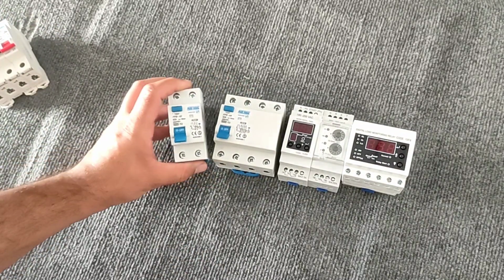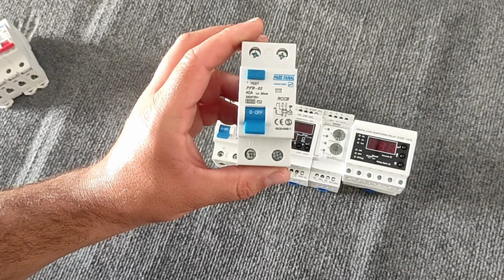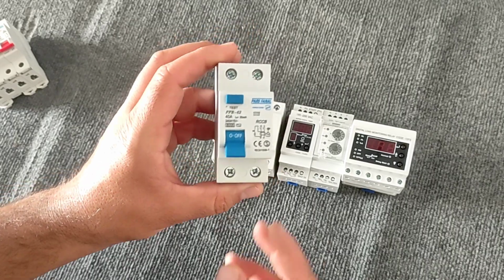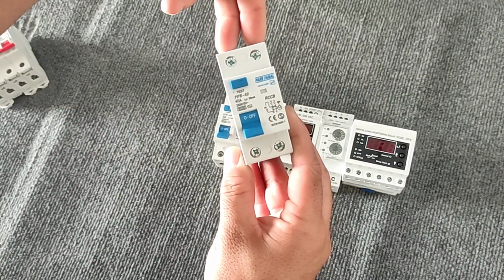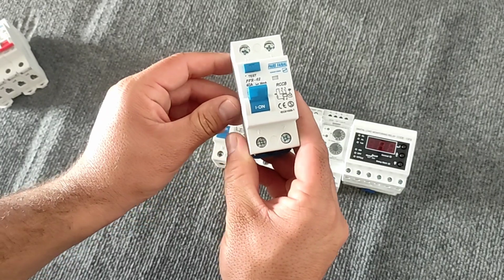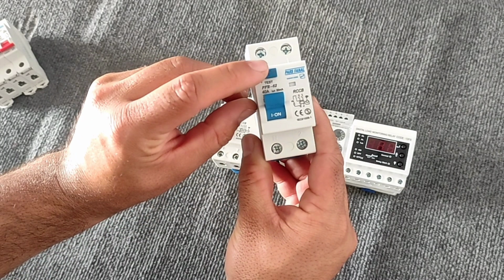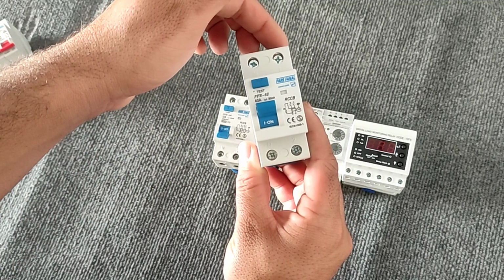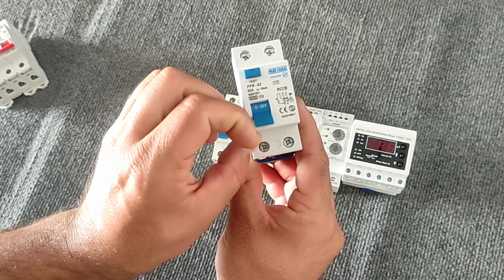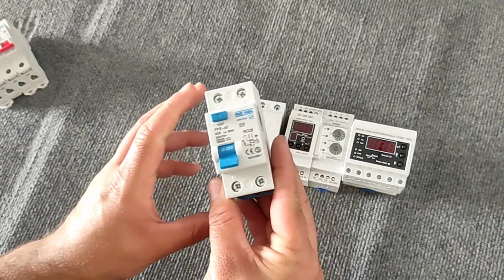The next device is a single-phase RCCB switch. The function of this switch is to protect the circuit against current leakage. This phenomenon protects people and animals from electrocution, so the use of these switches is recommended in all places, including industrial centers and homes. The phase and neutral wires enter the switch from this part and exit from this part. A test key is also installed on these switches, which tests their health. If the switch is connected to electricity and we press this button, the switch must be disconnected. Otherwise, it's broken.